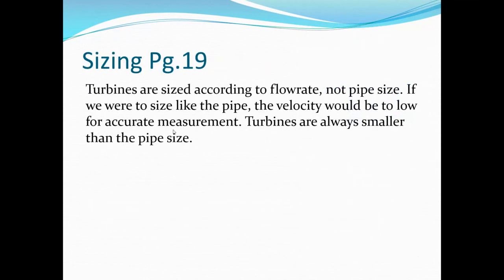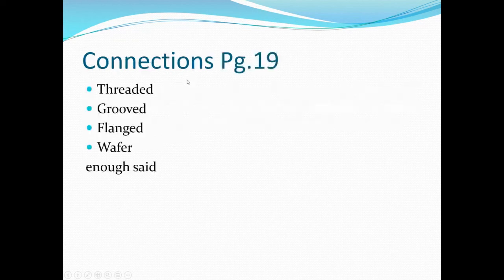Sizing: turbine meters are sized according to flow rate, not pipe size — they are almost always smaller than the pipe they're installed in. If sized the same as the line, velocity would not be high enough for proper operation. Connection types for installing turbine meters into piping include threaded, grooved, flanged, wafer, and other mounting styles.